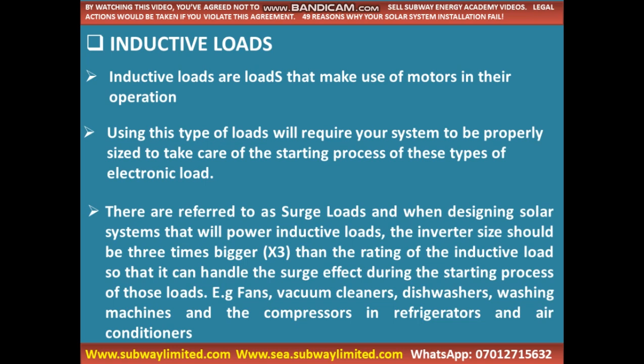Such loads are referred to as inductive loads. When designing solar systems that will power inductive loads, the inverter size should be 3 times bigger than the rating of the inductive load. So if you are using a fridge that is 1000 watts, your inverter size should be at least 3 kVA, so it can handle the start-up effects during the starting process of those loads. Examples are fans, vacuum cleaners, dishwashers, washing machines, and compressors in refrigerators and air conditioners. These are typical examples of inductive loads, like the fridge here.